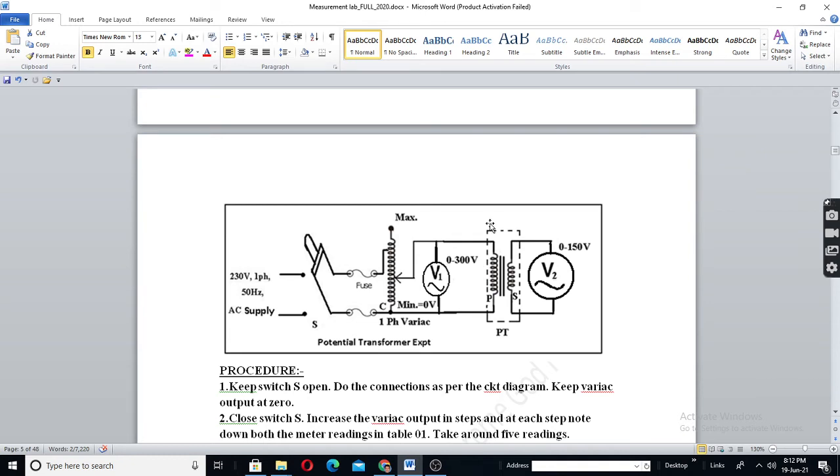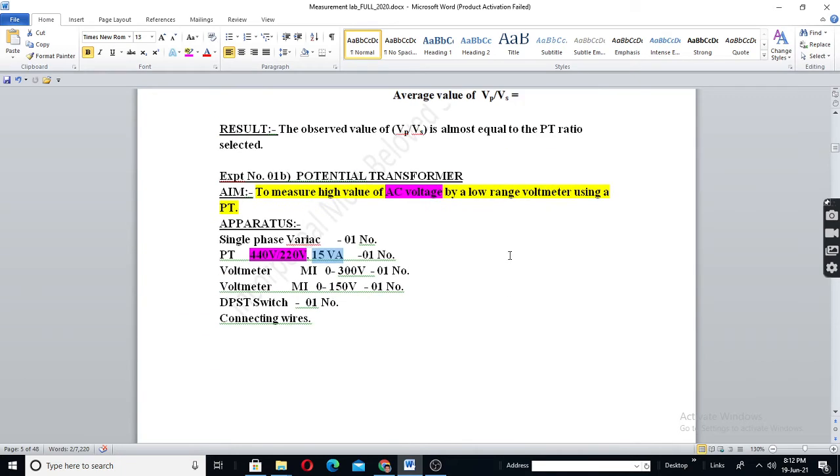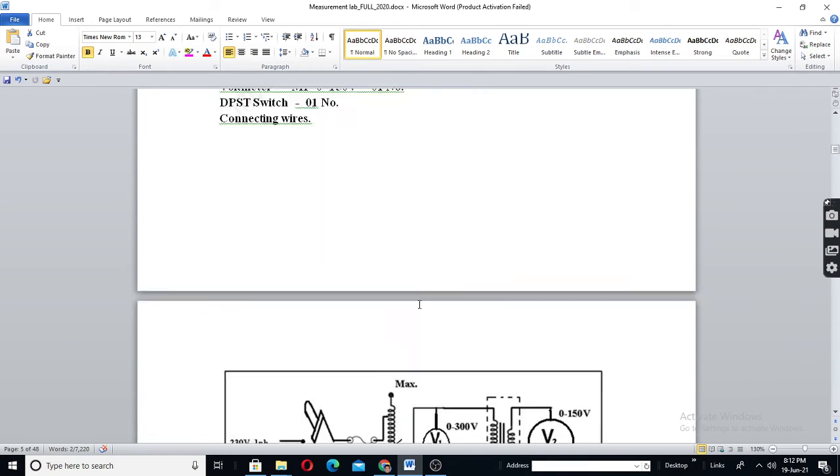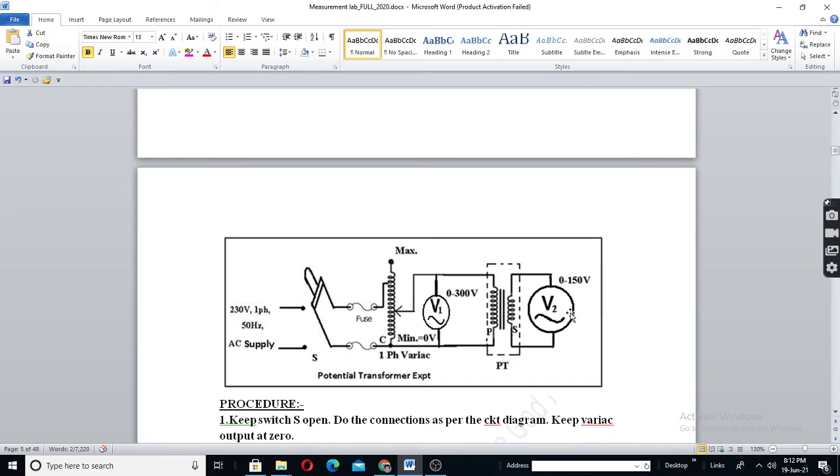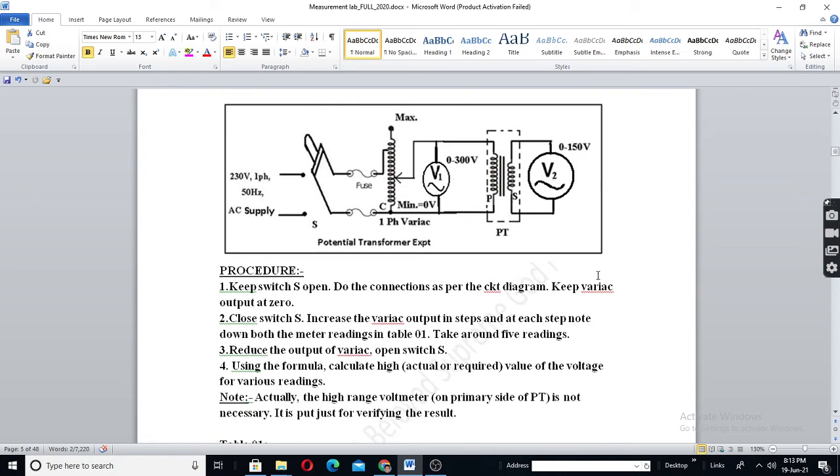If this is say 100, here it is 2 is to 1. Then what reading we get? V2. V2 multiplied by 2 will be equal to V1. So, if there is no V1, you can calculate V1 just by reading V2 and multiply by 2. Because, this is 440 by 220. So, here this will be low range voltmeter. Since this is 2 is to 1, we will have here 300 volts, 150 volts.